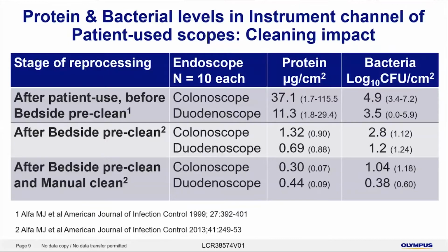And that's a very high organic load, which is not surprising, because the endoscope has been used on a patient and material has been suctioned up that instrument channel. For the bacterial load in CFU per centimeter squared, the average for the colonoscopes was 4.9 logs per centimeter squared, and that's a lot of organisms in a very small area. And the range, as you can see, went as high as 7 logs per centimeter squared. And for duodenoscopes, the average was 3.5 and went as high as 5.9.